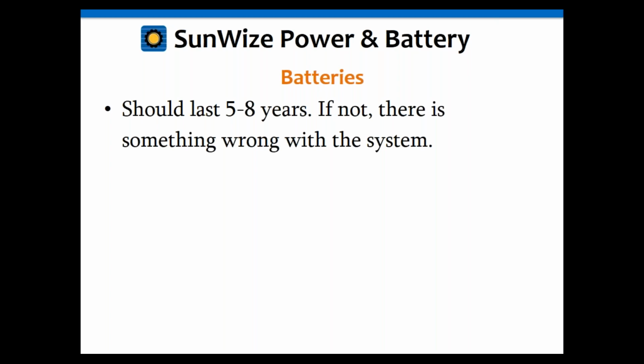Solar modules can last between 10 and 20 years or even longer. Charge controllers can last between 5 and 10 years or longer, and the battery should last 5 to 8 years. But we're hearing a lot of stories about batteries failing in the first year or two. So again, we're focusing on those, and we've gone over this a lot with regards to sizing of batteries, charge controllers, charging parameters, and things like that in a lot of the previous webinars.